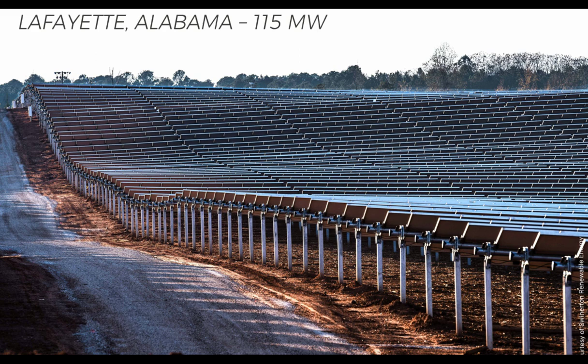On the following slide, here is just another picture of the undulating terrain. You can really see, obviously it's a single axis tracker, so those rows are on north-south axes. So this is an east or west facing slope. When the sun is setting on the horizon of this picture, with traditional backtracking, many of those rows on the slope are shading one another. The more optimal configuration is to turn them a little bit flatter and allow the entire block to maximize energy production, even though you might be reducing energy production on the very top row of that hill.